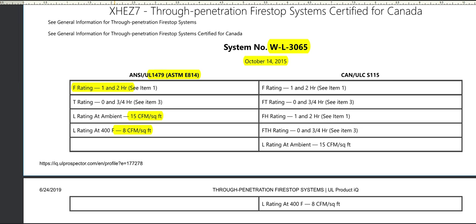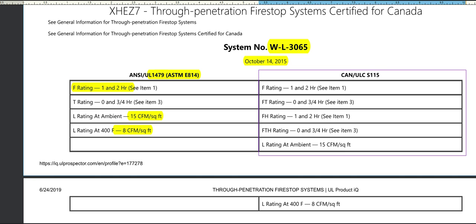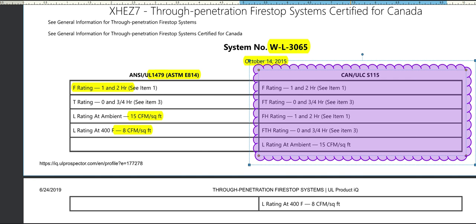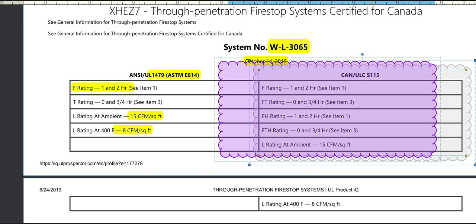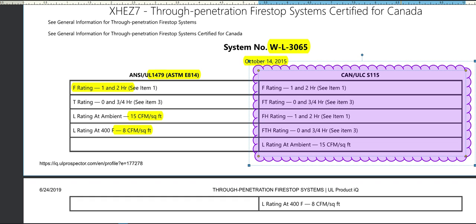There are additional ratings that may be required by code. An L rating is optional, and as you can see, there are two different measurements — ambient room temperature and at 400 degrees. If my barrier is a smoke barrier, I may need to do additional calculations to verify this system is acceptable. Also note that the product and system L ratings are not the same number. Additionally, UL listings now provide both Canadian and United States standards within the same document.